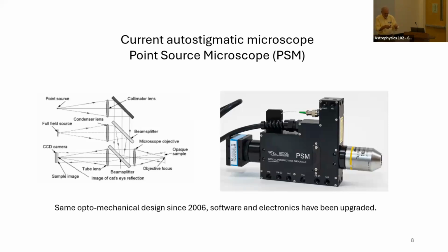Yeah, and in fact, this is why you want to go back and do the electronic setting of the crosshair, because every time you screw the objective in and out, that boresighting changes by maybe 5 microns. So how do you do that? You just put a surface here. It brings the spot back onto the camera, and you click the set reference.